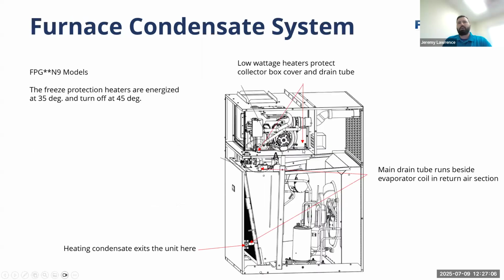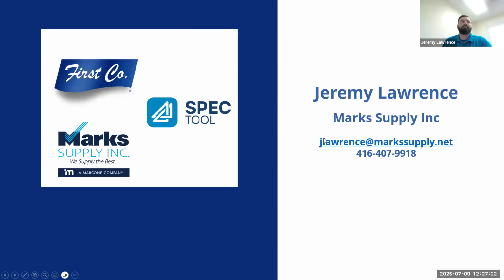Because these systems are meant to operate in cold temperatures, they've added 2 extra low wattage heaters within the condensate system to ensure predictable condensate flow throughout the winter operation. And that's it. Very quick product overview. Happy to dig into any of the details.